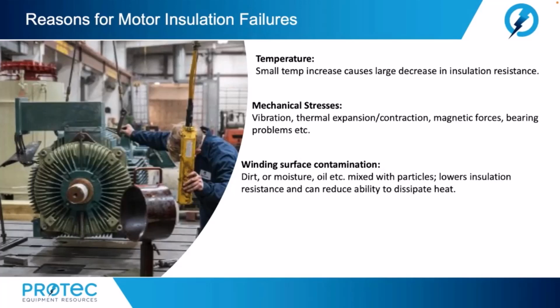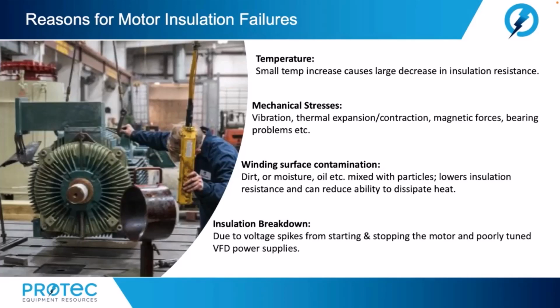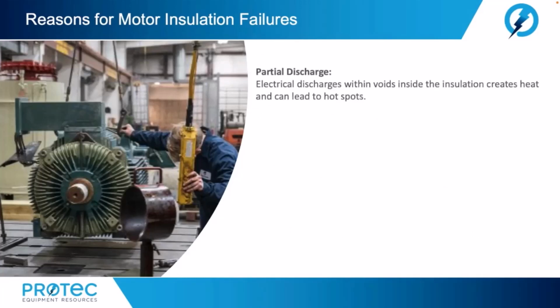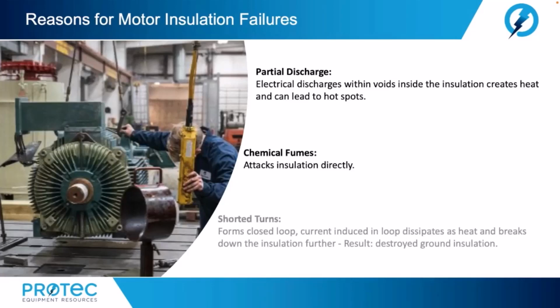Or the failure might have been winding surface contamination, dirt or moisture, oil, etc., mixed with particles. It lowers insulation resistance and can reduce ability to dissipate heat. Also, insulation breakdown due to voltage spikes from starting and stopping the motor and poorly tuned variable frequency drive power supplies. Other failures could be partial discharge, electrical discharges within voids inside the insulation that create heat and can lead to hot spots. Or the failure could have been chemical fumes. These attack the insulation directly. Possibly shorted turns. These form closed loops. Current induced in loops dissipate as heat and breaks down the insulation further. The result, destroyed ground insulation.